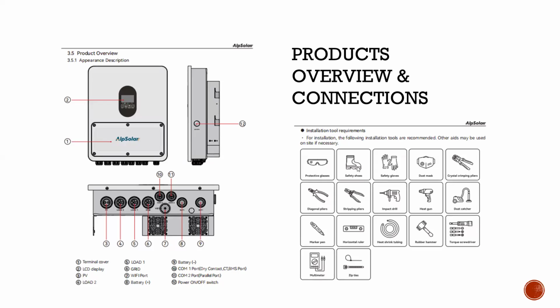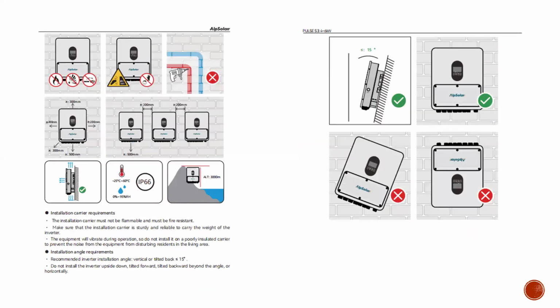And of course, one of the things I would like to say in the next slide is the installation angle. Actually, the best angle to install an inverter like this is to tilt it about 15 degrees backward a little bit, right? But of course, we know that we will not always have the opportunity to have this kind of angle. That is why you can also make it sit comfortably on your wall, right? It should not bend to the right side or to the left side, like you see, or be stored upside down. This is not accepted and it's not good for the system.